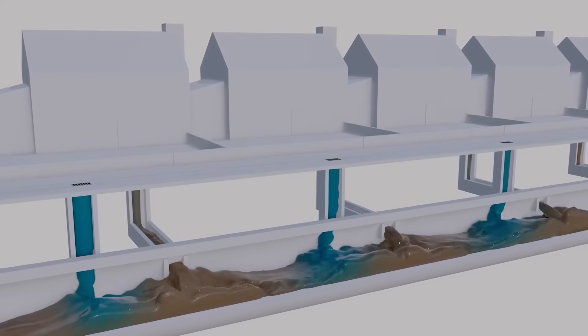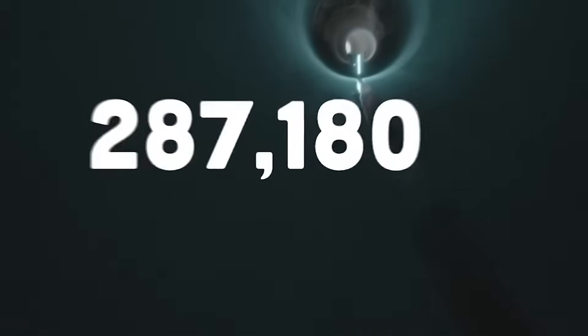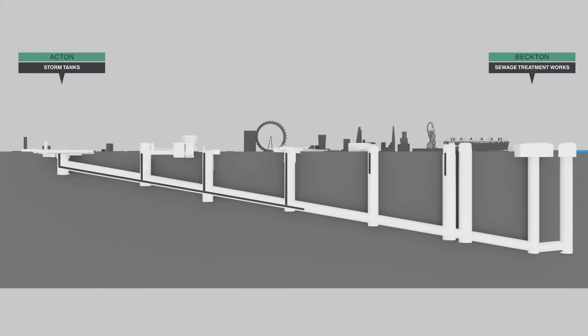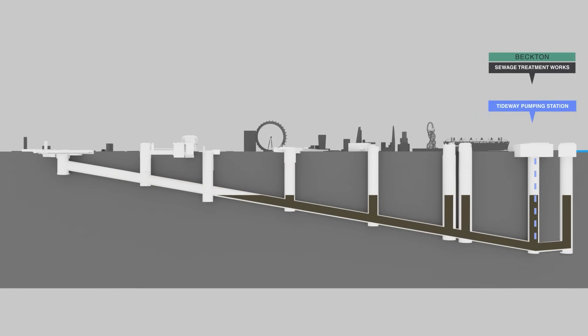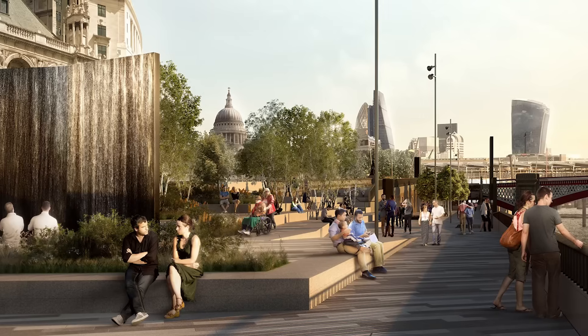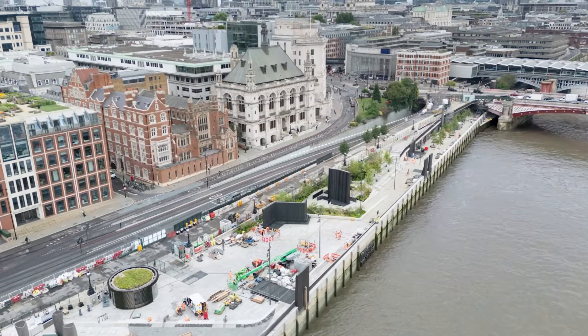The tunnel's purpose is straightforward but powerful—it intercepts sewage from the city's most polluting overflow points before it enters the Thames. In total, 34 combined sewer overflows are connected via shafts and smaller linked tunnels. When heavy rain overwhelms the existing system, instead of spilling into the river, the flow is diverted into the Tideway Tunnel. The tunnel can hold up to 1.6 million cubic meters of water—equivalent to nearly 600 Olympic swimming pools. Once storm pressure subsides, the flows are pumped eastwards through the Lee Tunnel to Beckton Sewage Treatment Works—Europe's largest sewage treatment facility. Beyond its core function, the tunnel also delivers a visible legacy on the riverfront, including the Bazalgette Embankment at Blackfriars—the first new riverside embankment in 150 years.